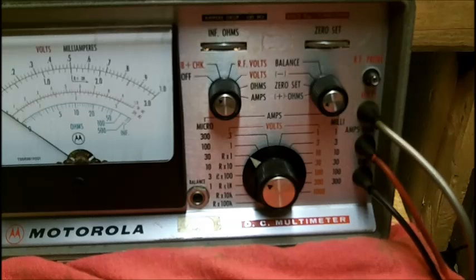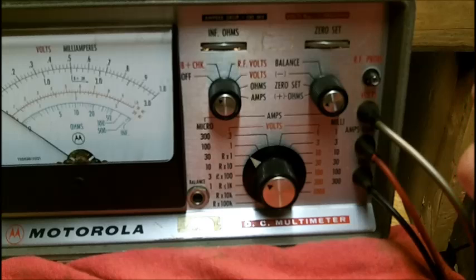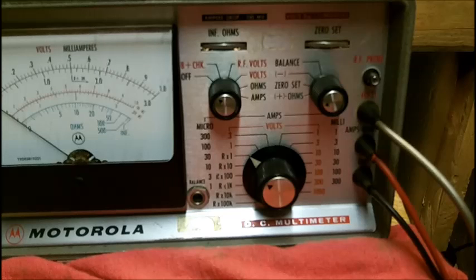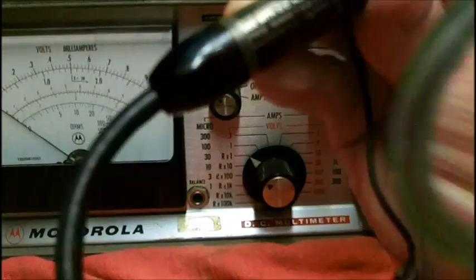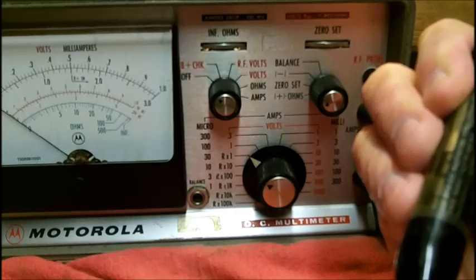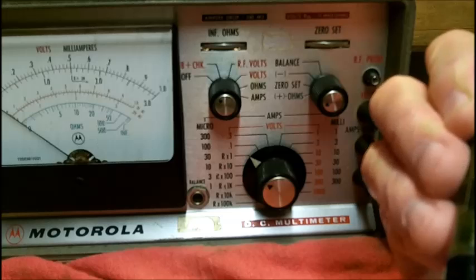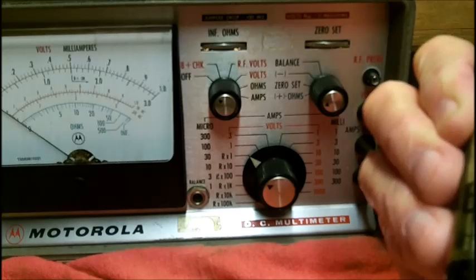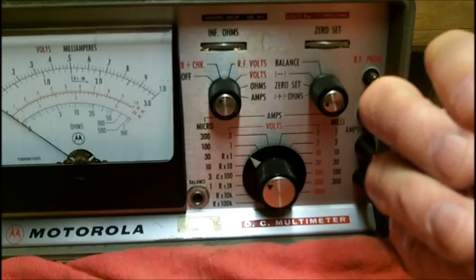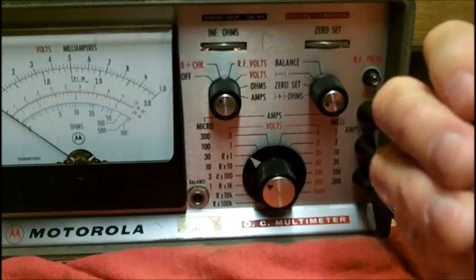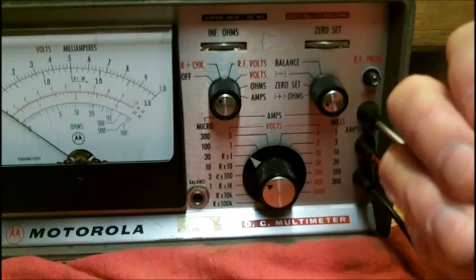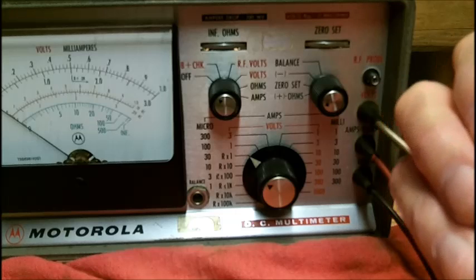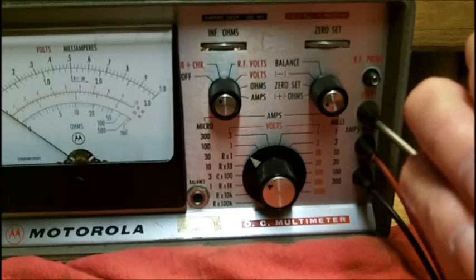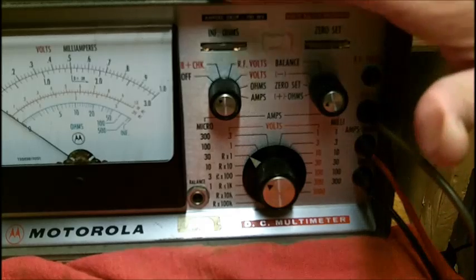This is a Motorola RF probe, model SLN6055A. That's the Motorola part number for this. Frequency range 1 kc to 400 megacycles, right here. Doubt you'll be able to see that. Maximum DC voltage 400. Maximum AC voltage 10 volts. Motorola Incorporated, Chicago, Illinois. It says here to be used with the DC multimeters models S1052B and the S1063A. This is the 1052B.